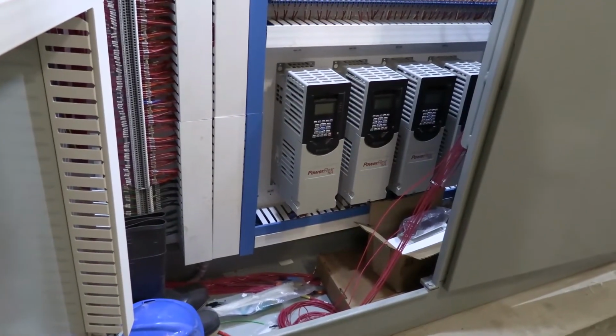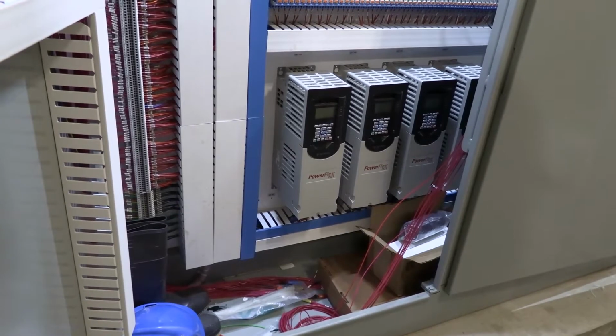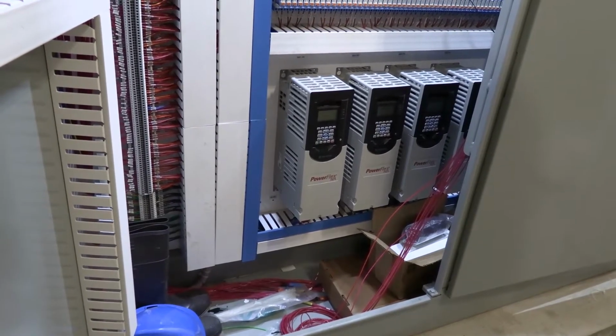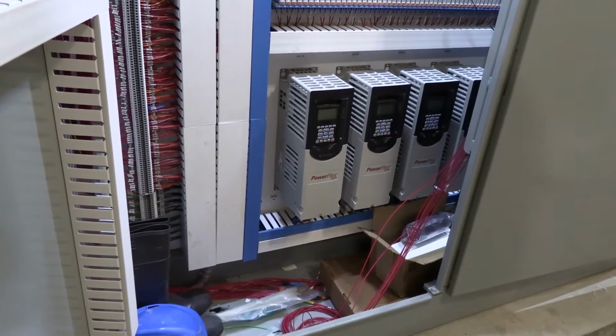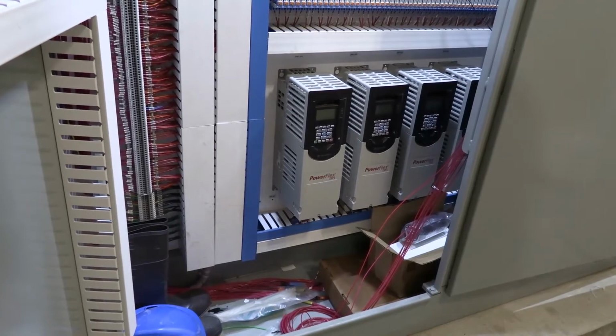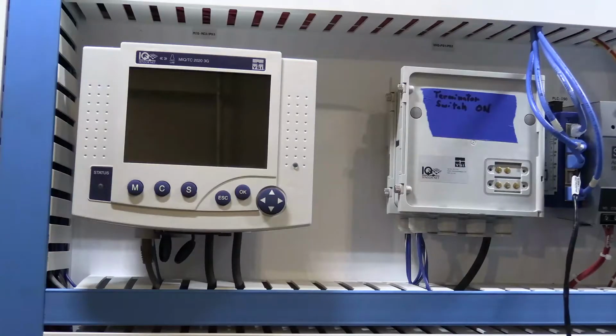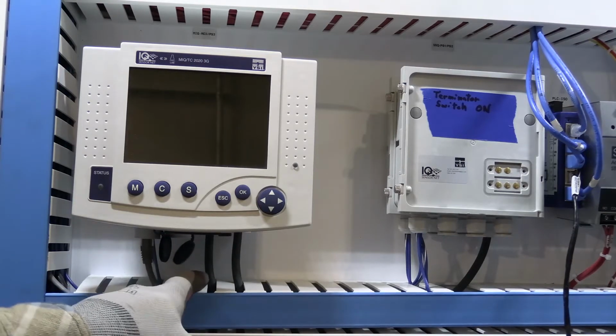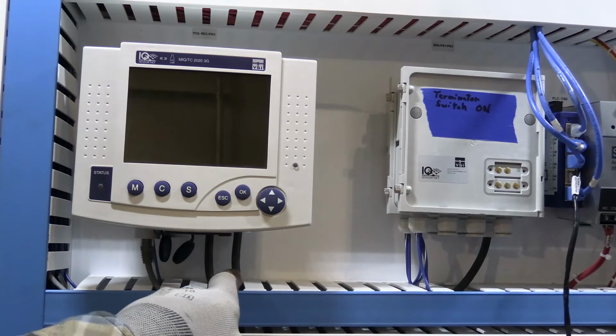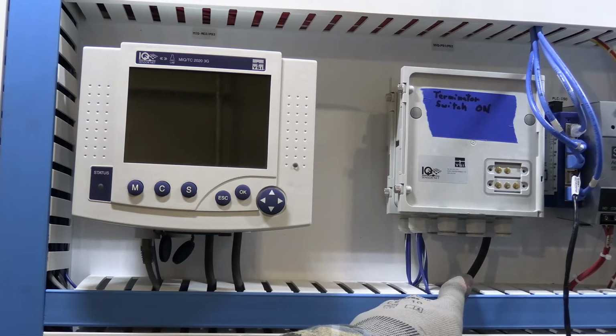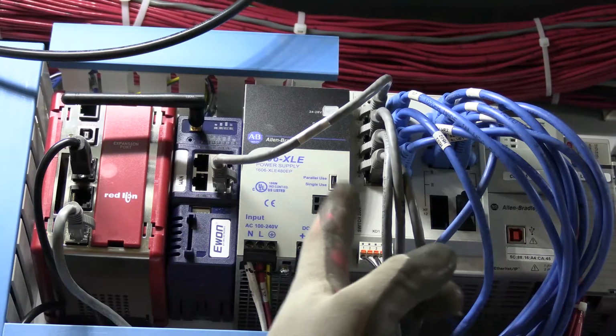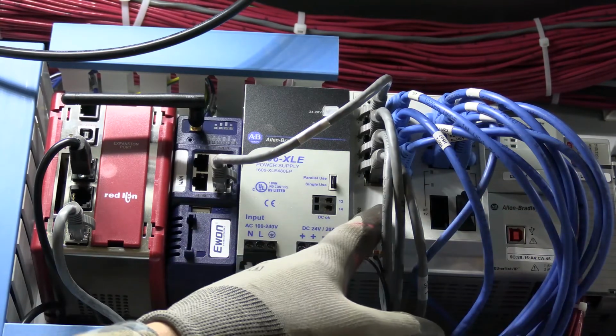For larger panels, sometimes we have field termination blocks on the bottom. There is none on this job, but if you do have those on yours, make sure you take pictures of those too. If your job has it, another picture required is of the YSI sensor net. You can see below here we have the special sensor net cable, and that's what we'll be looking for in the picture. You can see all the Cat 6s coming in here to the network switch.